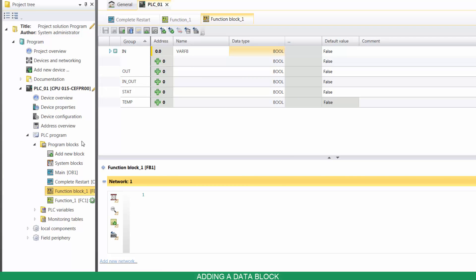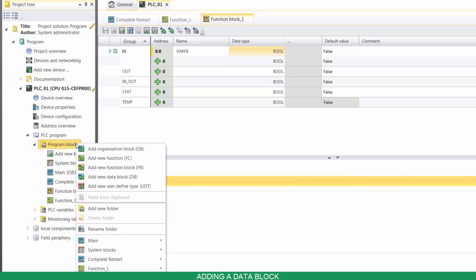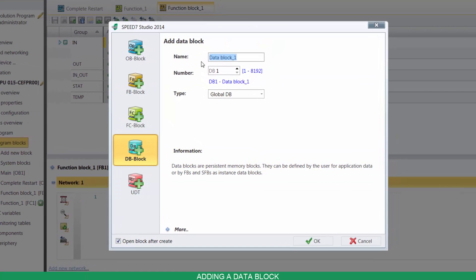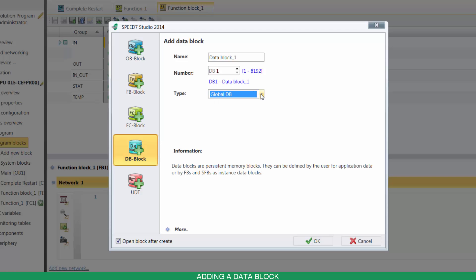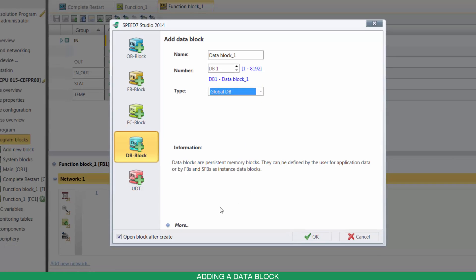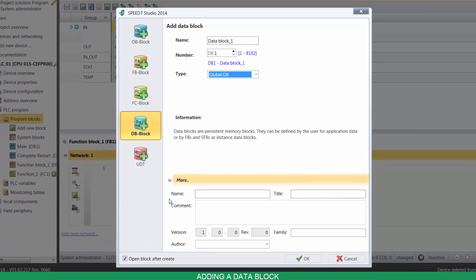To add a new DB, right-click on Program Blocks, then click on Add Data Block. You can name it, select its number, and choose its type — Global DB, so that all blocks have access to the data, or Instance DB, so that only the assigned FB has access to the data. If you click on More, you can enter further details.